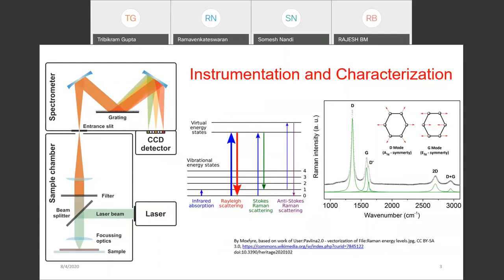Raman is suitable for analysis of non-fluorescent compounds and inorganic crystalline compounds. Confocal Raman microscope provides submicron spatial resolution in X, Y and Z axis. Raman scattering is recorded only in the low energy side to give Stokes scattering. Anti-Stokes lines are appreciably less intense compared to Stokes lines, and that is why only the Stokes part of the spectrum is used.